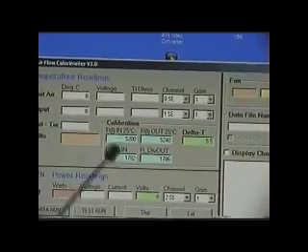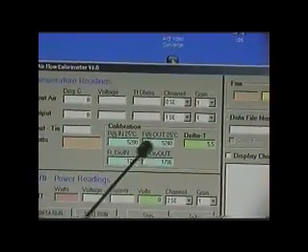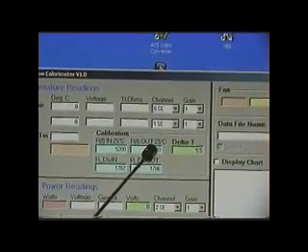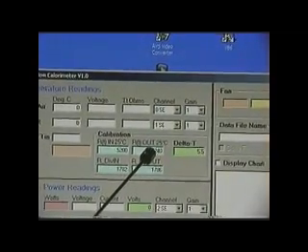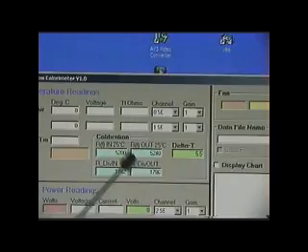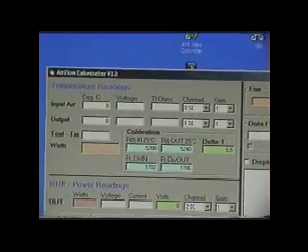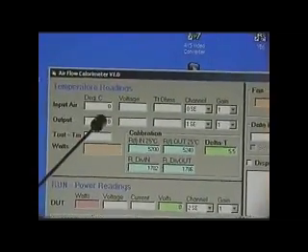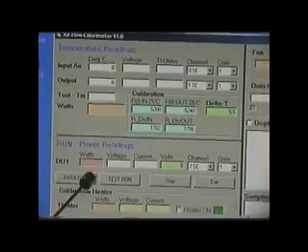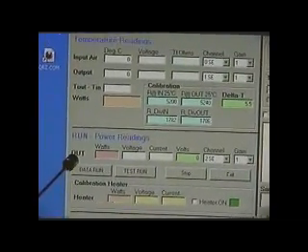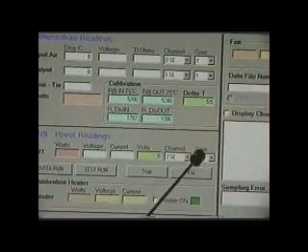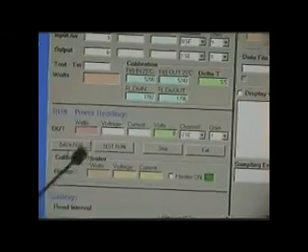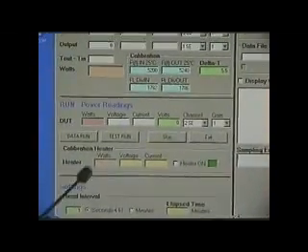So I have this on the screen so that I can change these two readily. Also, if I change out thermistors, depending upon the percentage of accuracy of the thermistor at 25C, this will change also. So I have that so I can change those fields. But the wattage is derived through calibration, so as these temperatures change, this wattage will change. Down here, this is the field for the DUT, the device under test, and it will show the current, the voltage, and the wattage of the actual device based upon this temperature differential from up here.